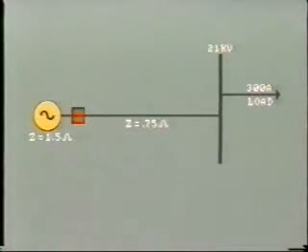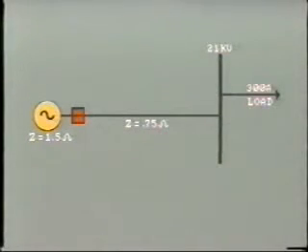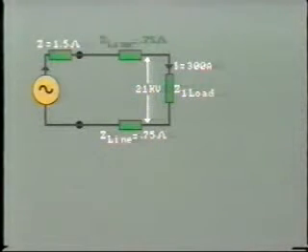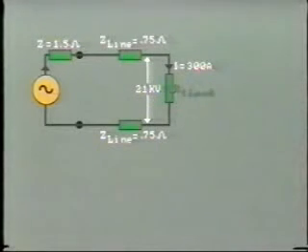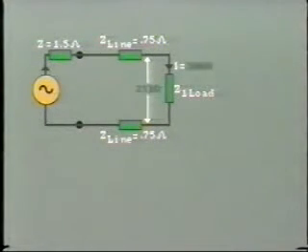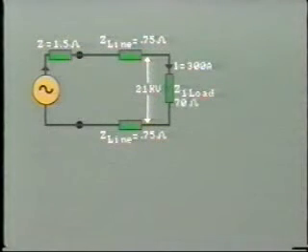In this simple one-line diagram we have a generator feeding power through its circuit breaker and transmission line. The load is 300 amps at a phase to neutral voltage of 21 kV. For simplicity let us draw this out as a single phase circuit. This 1.5 ohm impedance here represents that of the generator, while the 0.75 ohms here represents the impedance of the transmission line. As this is single phase we can calculate the impedance of the load by dividing 21 kV by 300 amps, which comes to 70 ohms.